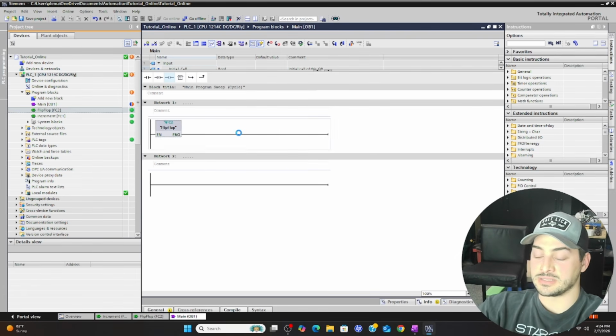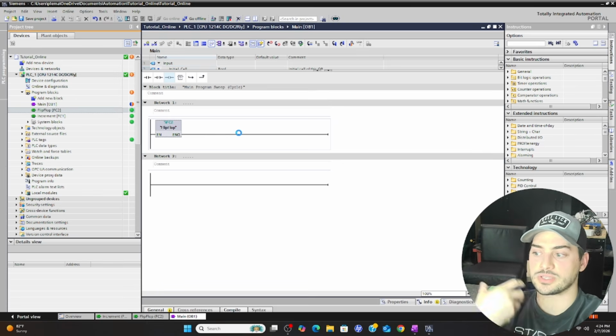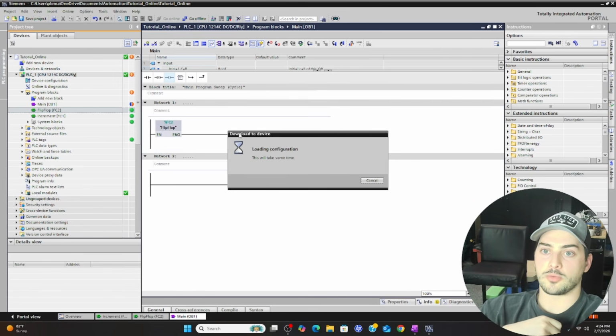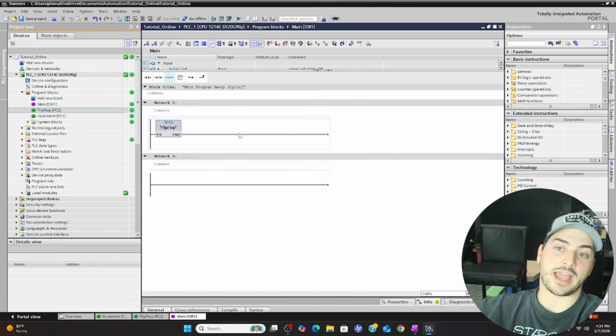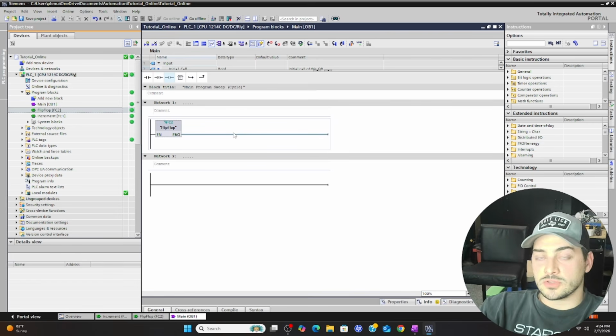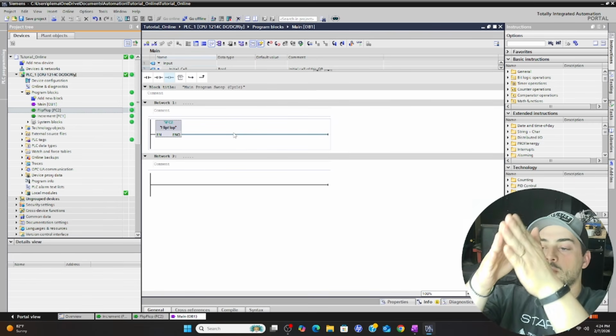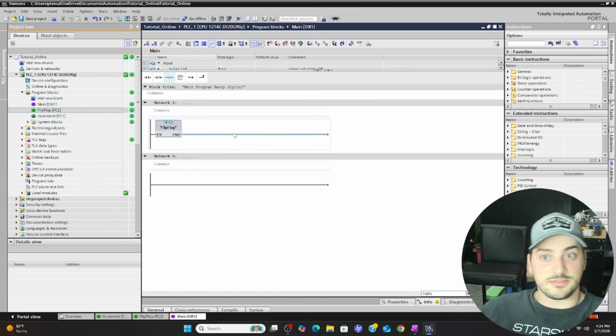It's usually in an industrial control cabinet, and it's usually controlling real world outputs, and you're immediately changing how they will react. So most of the time before you download to a controller, you want to power that device into a completely safe and idle state.